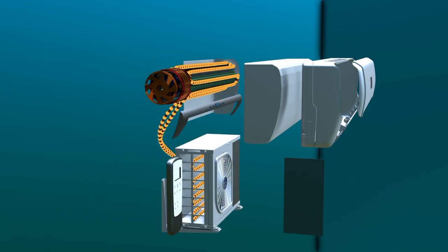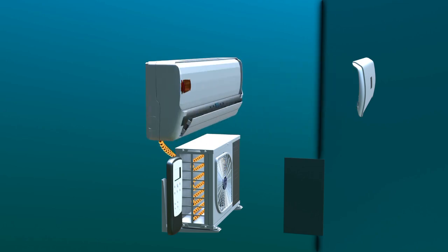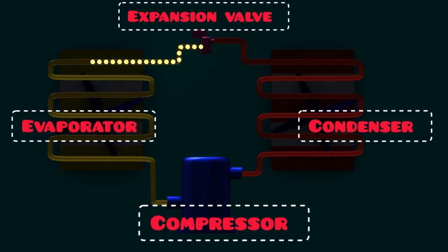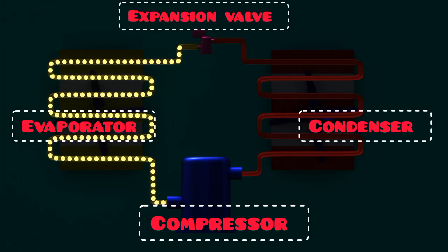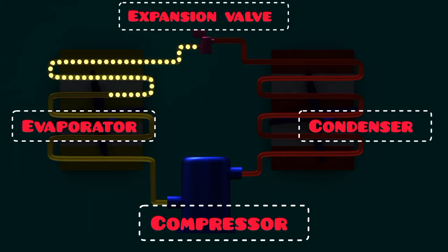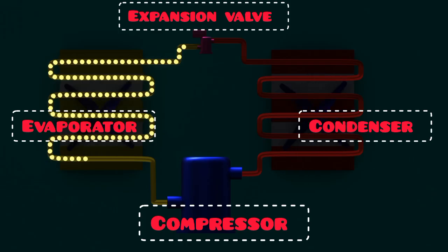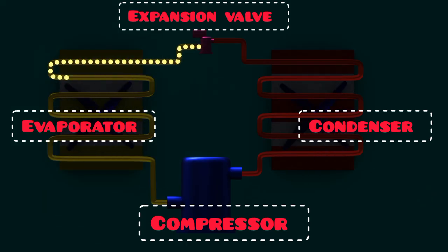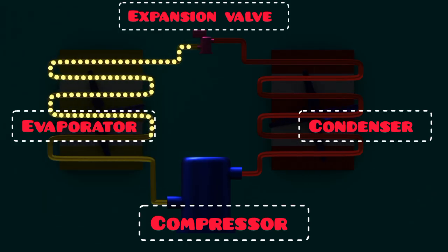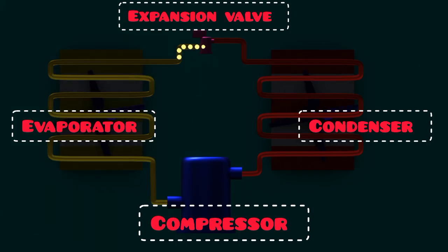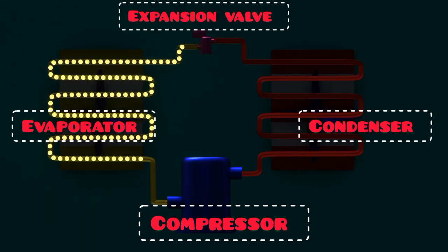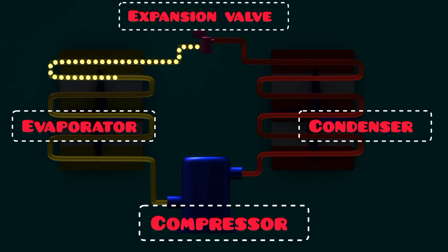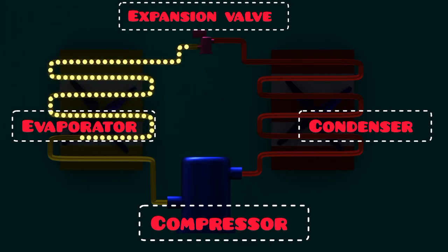This condition is extremely important for system safety. Liquid refrigerant entering the compressor can cause severe damage. The compressor contains an electric motor, and liquid refrigerant is incompressible. If liquid enters the compressor, it can lead to mechanical failure or electrical short circuits, resulting in serious damage. Therefore, the system is designed to ensure that only vapor reaches the compressor.